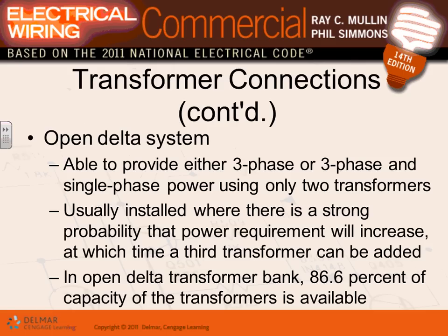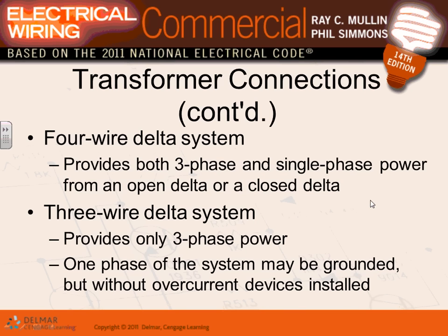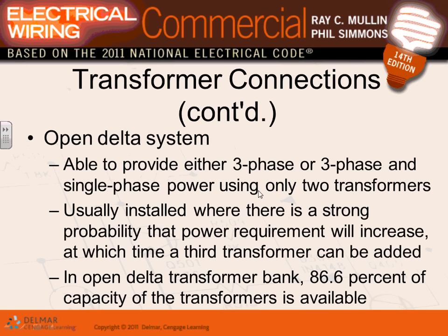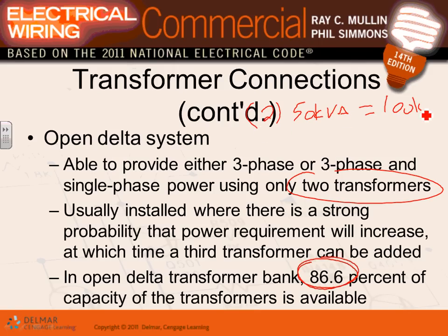Here's open delta. We talked about the open delta. Utilities use it. They have 2 transformers for the open delta. Adam and you guys wired them with us in the lab. We have 2 transformers to create a 3-phase system. The problem with them, Karen, is you have to derate them to 86.6 percent. So for example, if you have two 50 kVA transformers, that will get you 100 kVA, but you can only utilize 86.6 kVA out of it without burning it. Why? Because of the lack of a phase. So that's your open delta.